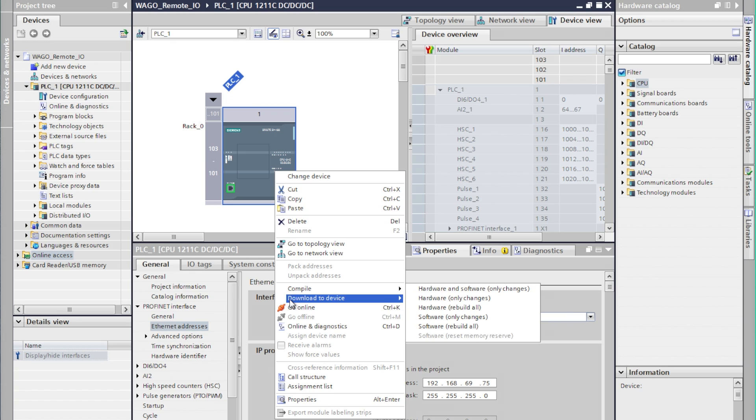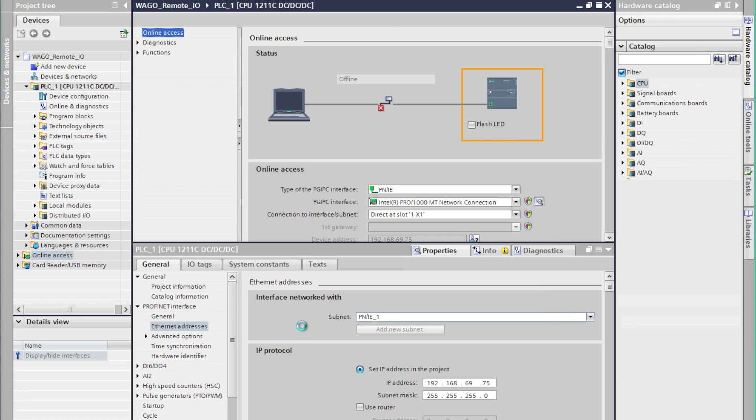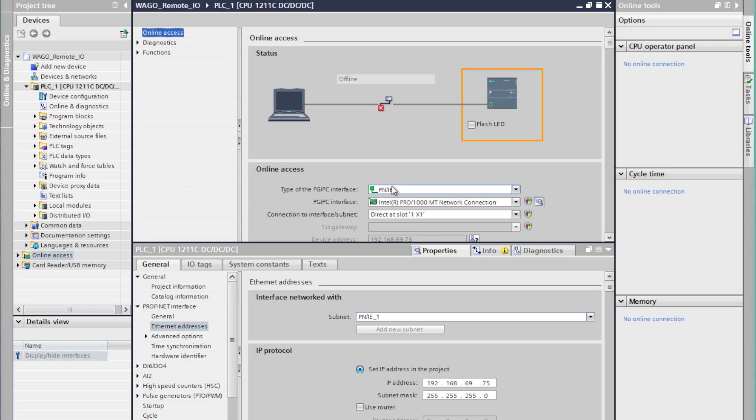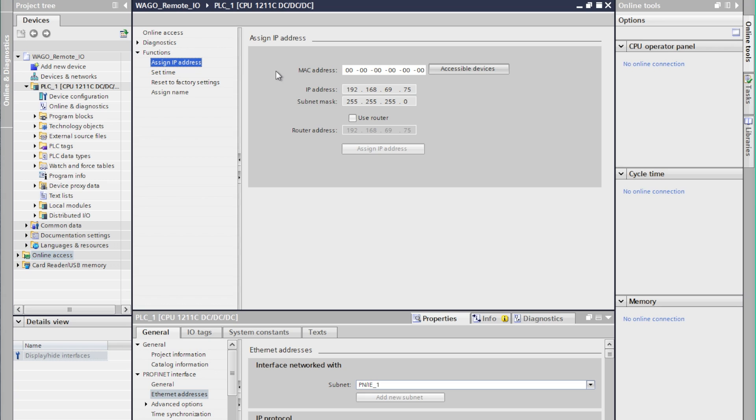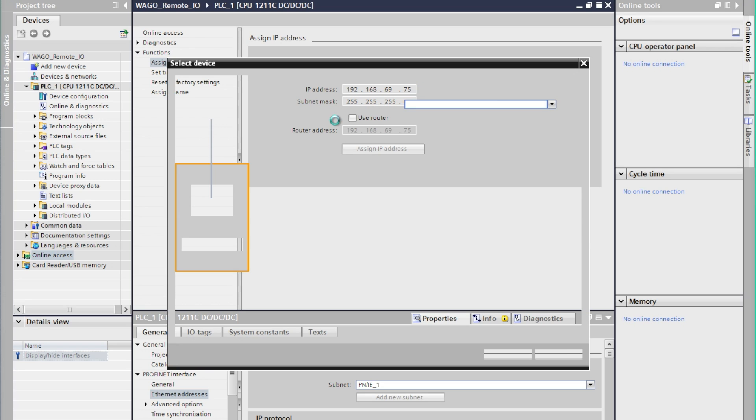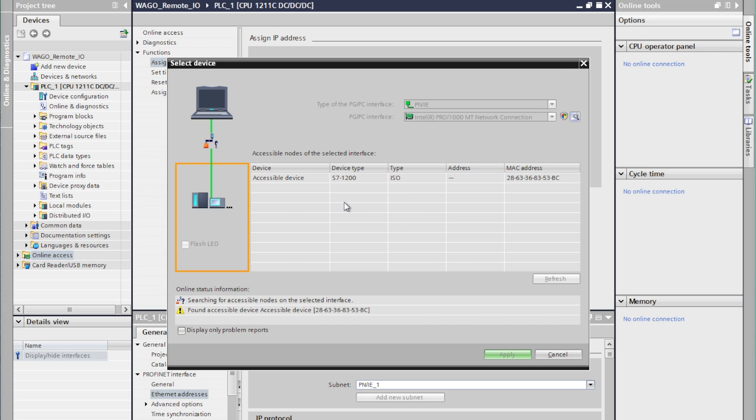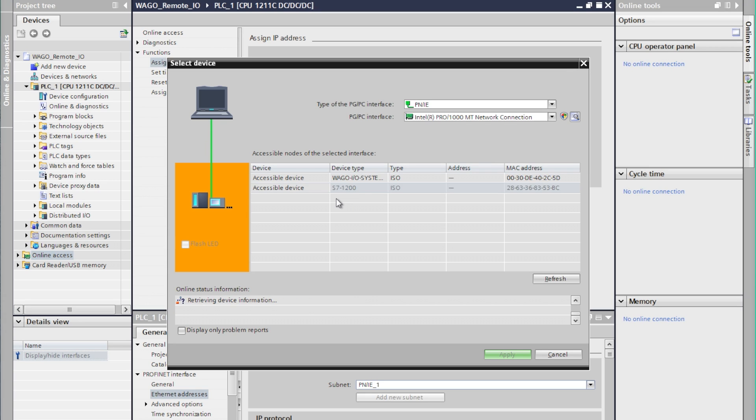Now by right clicking on the controller we'll select online and diagnostics and this will take us to the actual controller settings. We'll make sure our network settings are correct and then we'll expand the menu functions and select IP address. And one of the nice things of PROFINET is it has a network scanner so we'll scan the system and look for any accessible devices.